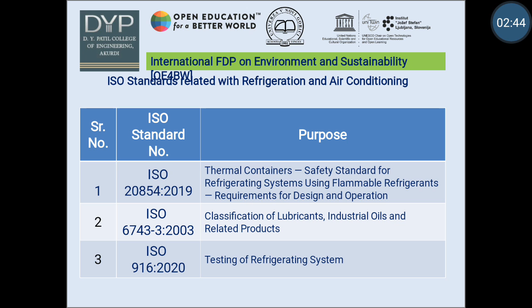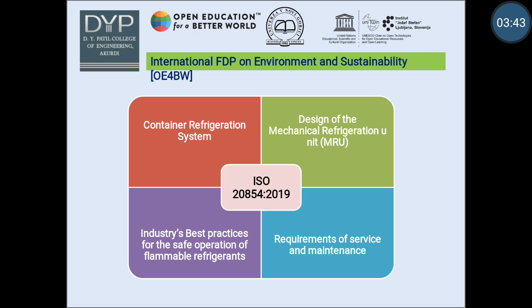Now let's see first ISO standard, ISO 20854 2019. Basically, the scope of this ISO standard is limited to container refrigerating system operated in conjunction with the carriage of refrigerated cargo. This document describes the design of mechanical refrigeration unit, that is MRU, and operation of container refrigerating system in all anticipated operational modes and locations. Also, it describes the industry's best practices for the safe operation of flammable refrigerants in refrigerating system. Finally, this document describes the requirements of service and maintenance when working with flammable refrigerant.